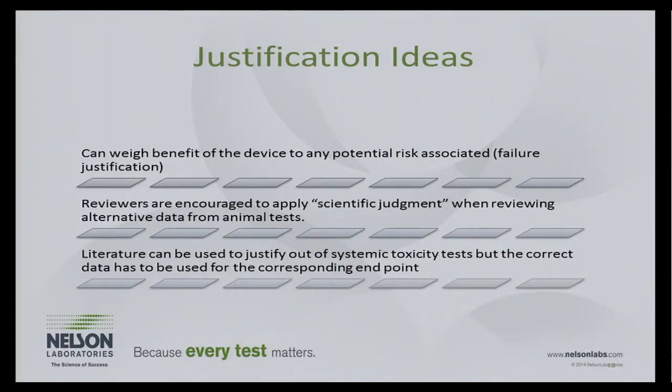If your device is going to prolong someone's life or is going to save someone's life, then you can be a little bit more toxic. You can have a little bit more impact in the biocompatibility tests and be able to justify those test failures, or even looking at carcinogenicity and toxicity a little bit differently because of the benefit to the patient.